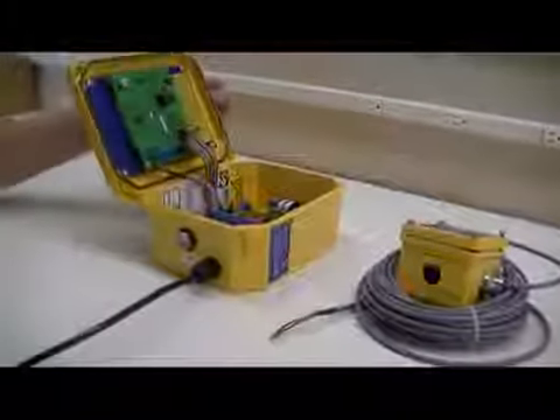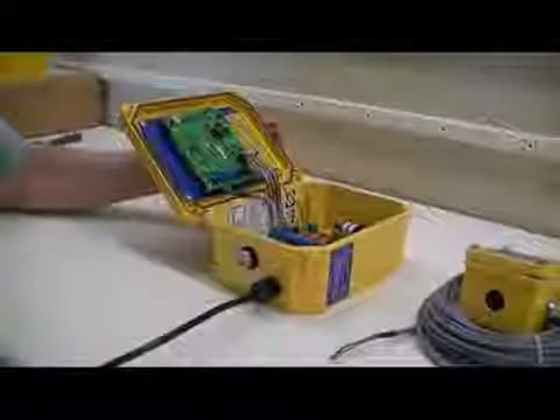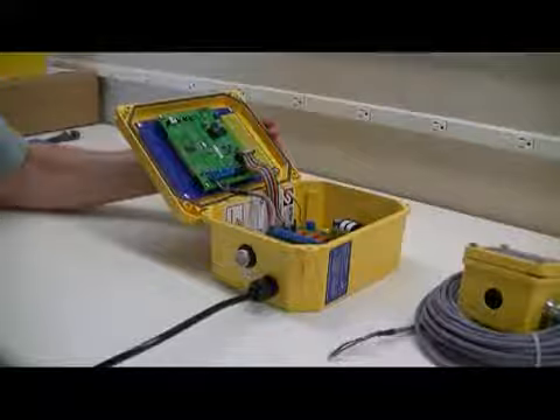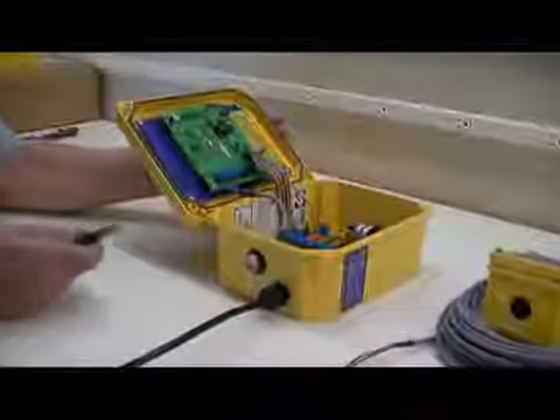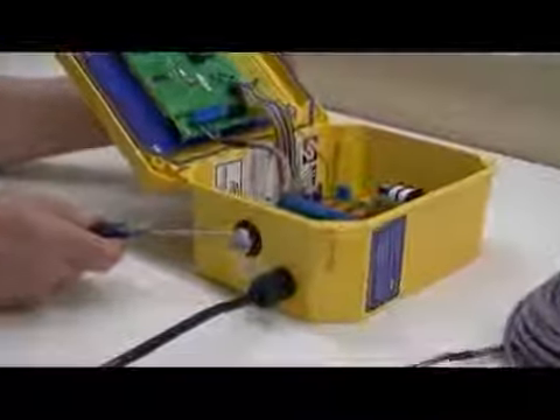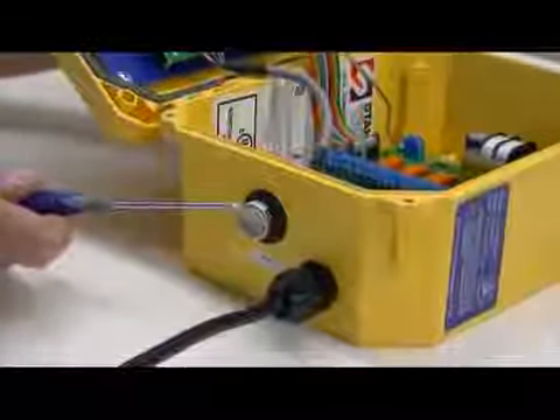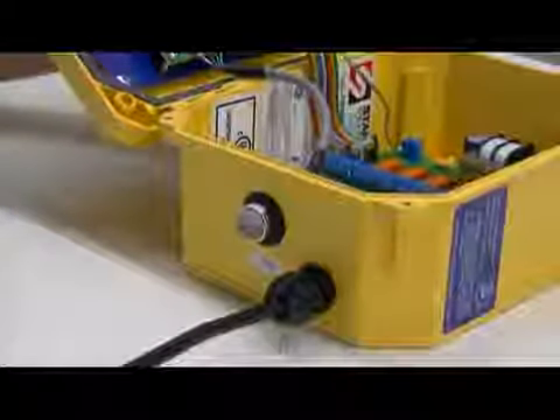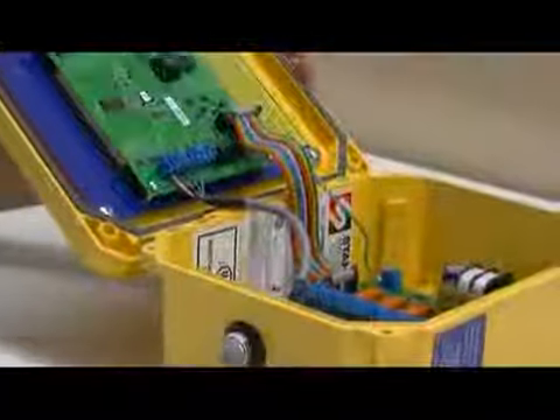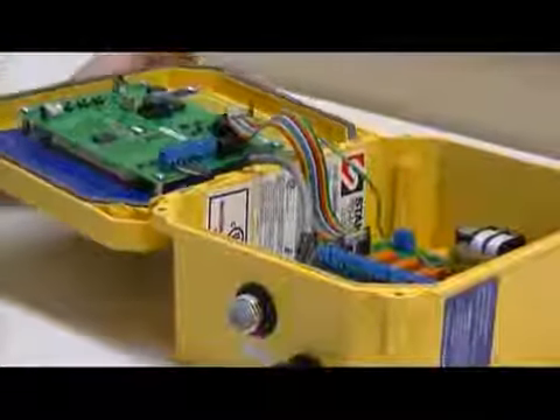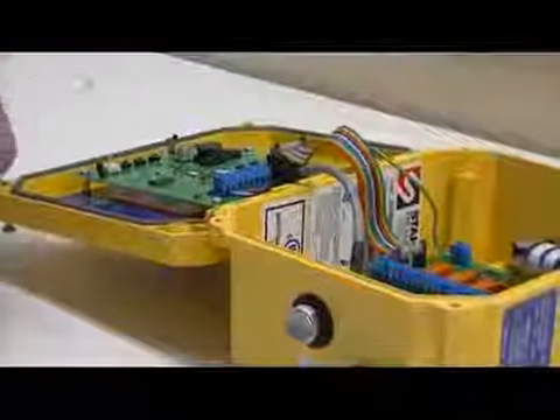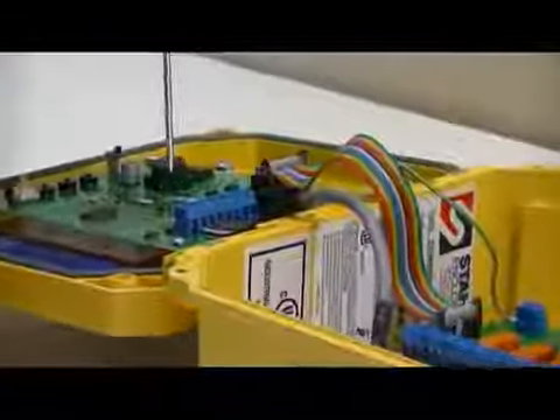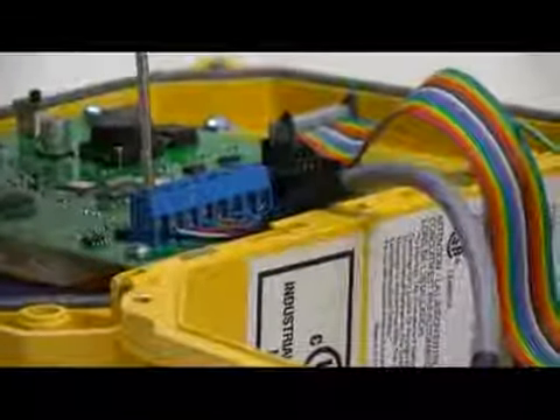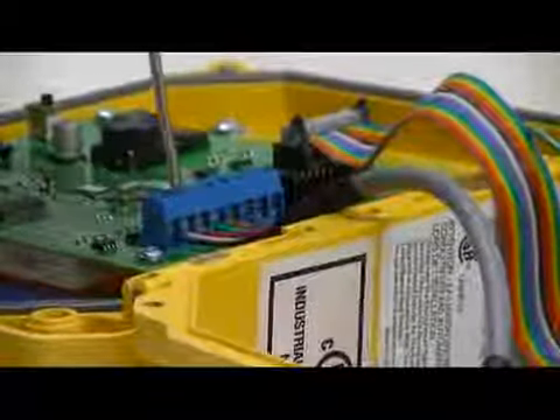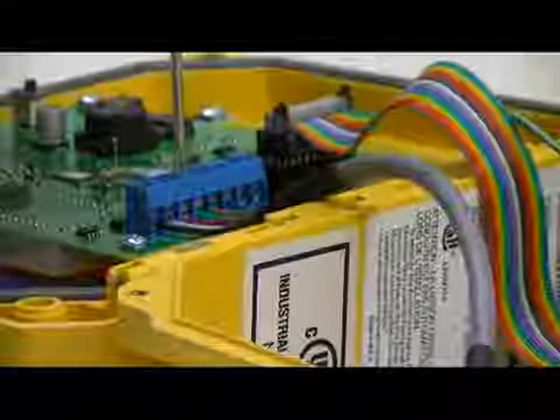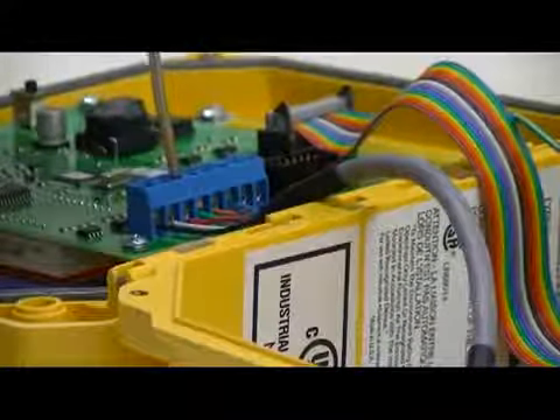Our units are designed for one sensor per unit. When we do a remote sensor, we are taking the local sensor off the unit and remote locating it up to 500 feet away from the detector box. We start by removing the local sensor pigtail in preparation for the remote sensor.